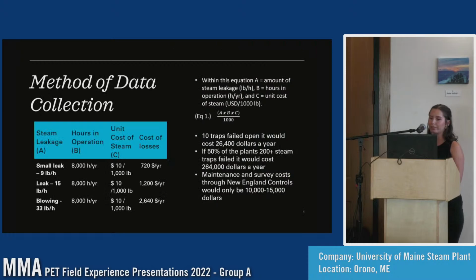So my method of data collection is, if you look under the steam leakage, which is section A, I got the averages of a small leak, a normal leak, and straight blowing steam. So a small leak is 9 pounds per hour, which is just one steam trap. And a normal leak is going to be 15 pounds per hour. And straight blowing is 33 pounds per hour. I use 8,000 hours per year because they are in continuous operation, and the unit cost of steam. And you can see in my equation 1 how I figured out my costs.